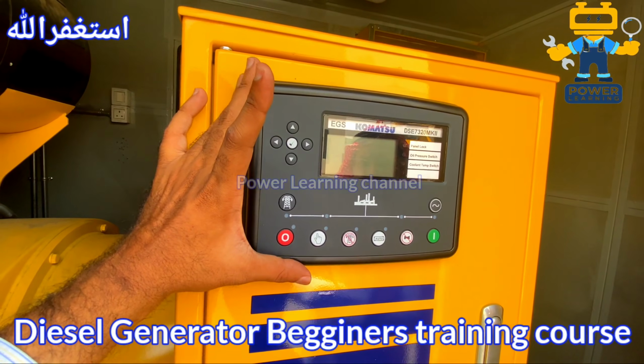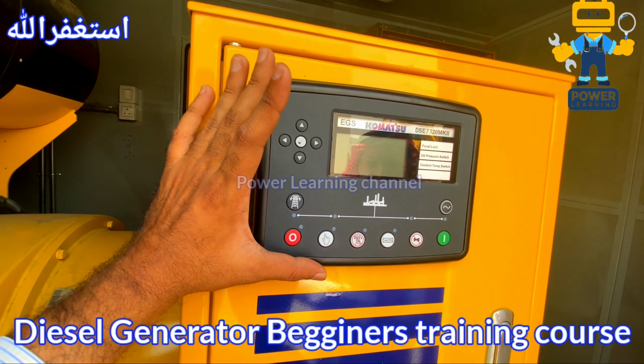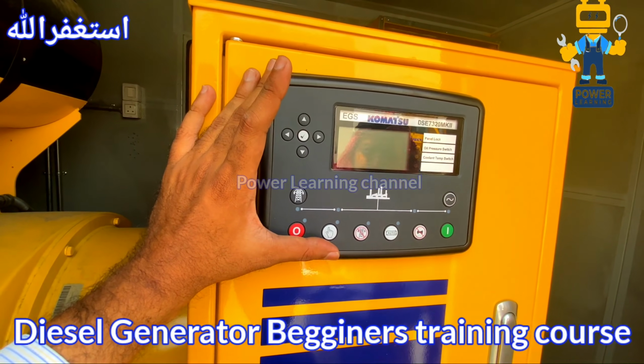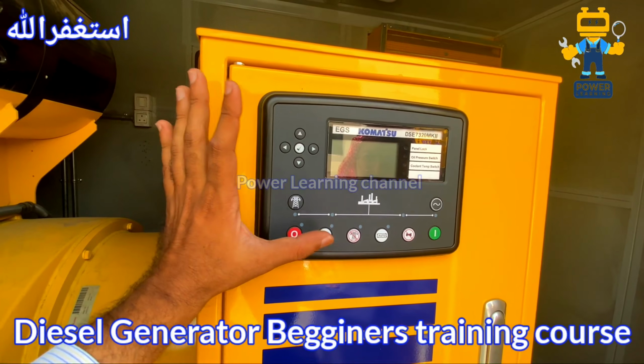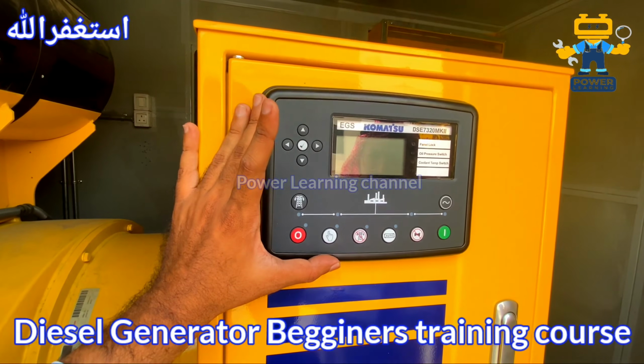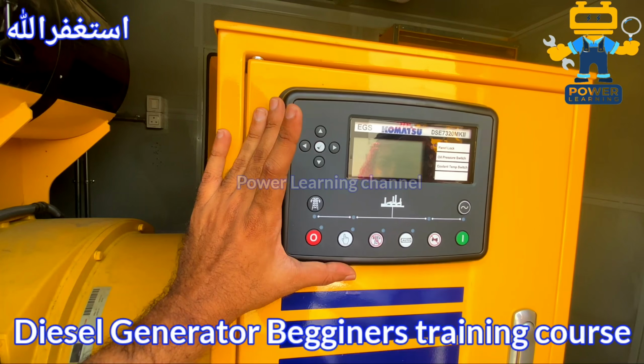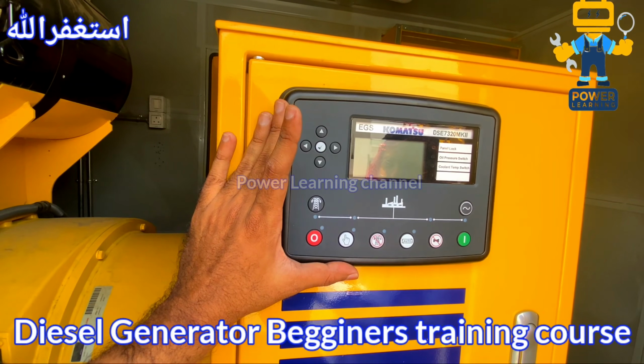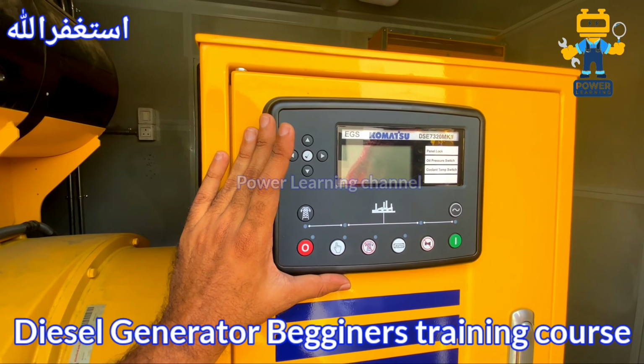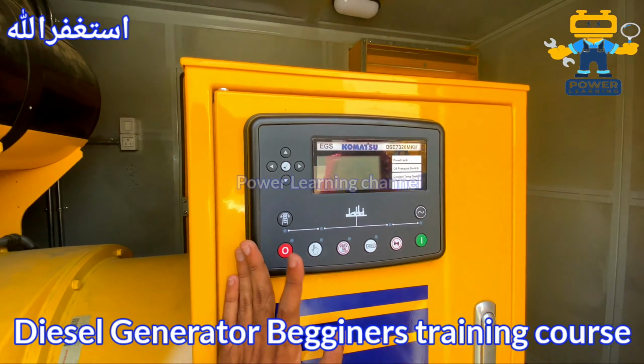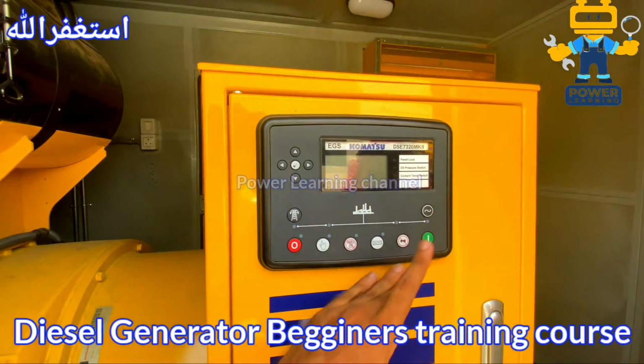This is a PLC based, microprocessor based controller. We can also start the engine from here, and stop it from here. This is called an AMF controller, auto mains failure controller. This controller can work automatically on demand of the customer in the event of power failure, and also manually by the operator.